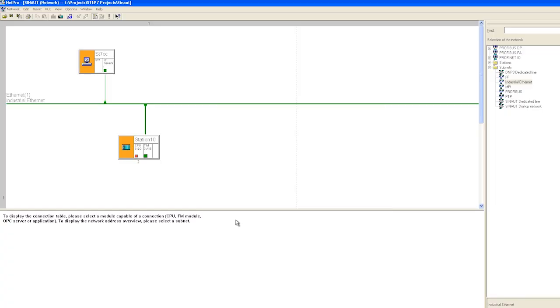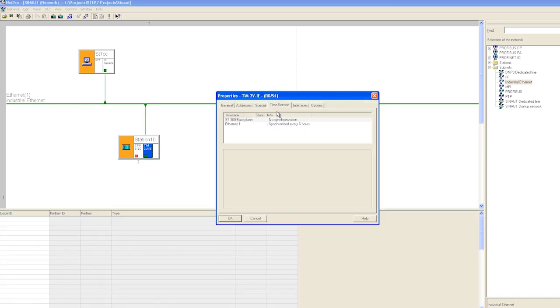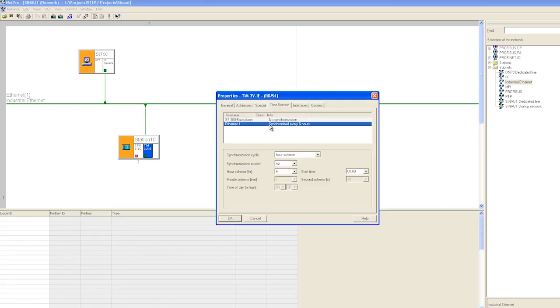modify the IP addresses. In the TIM object properties we set a time synchronization interval. This is the interval at which the control center provides the station with the precise time, for example 6 hours.